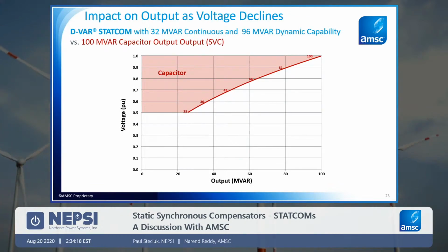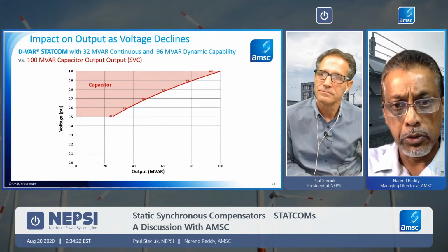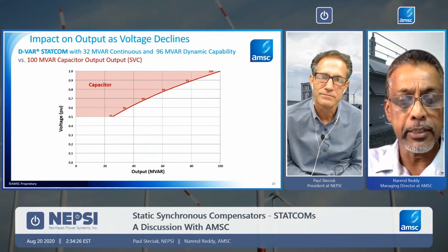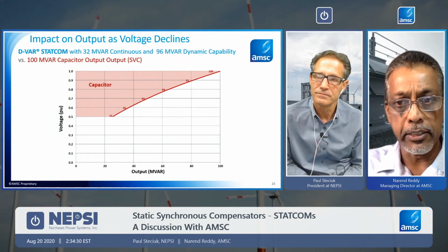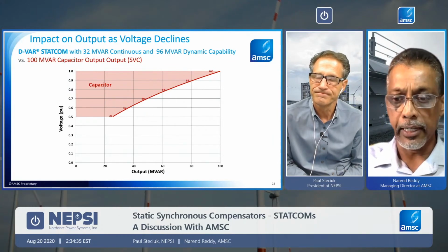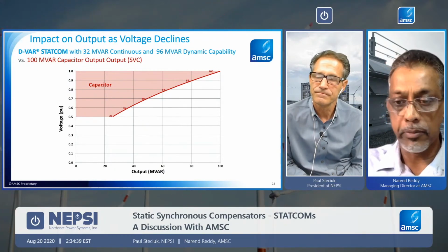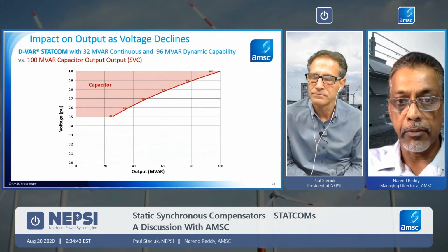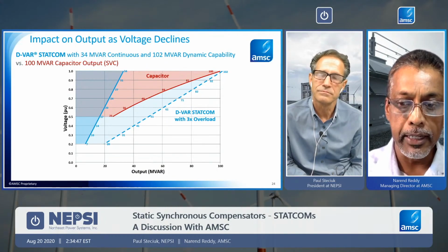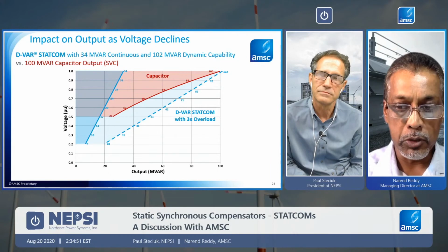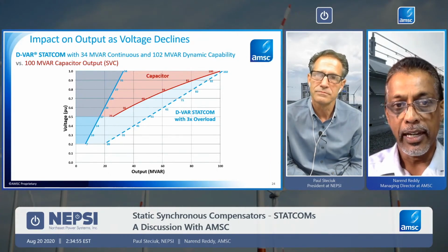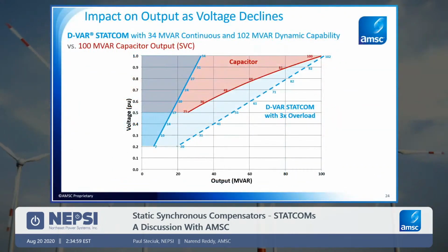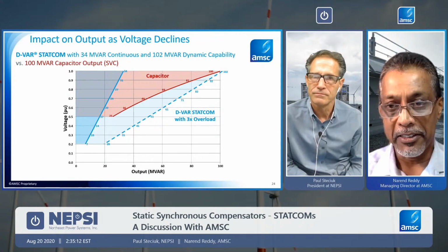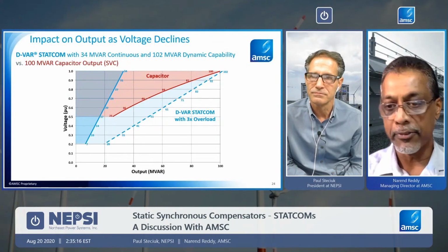What's interesting here is that this overload capability is something that we utilize to right-size the STATCOM solution that would be needed for an application. For example, let's say studies dictate that a 100 megavar SVC is required to solve the problem. If that amount of vars solves the problem, good. But then what this overload capability shows is that we utilize these 2 seconds of overload because that's what's needed during the transient period. That requires only about 34 megavars, or a third of that SVC capacity, to be installed. Yet you also have the full 3 times overload, so you get the 102 megavars for 2 seconds, but after that, you really don't need it.